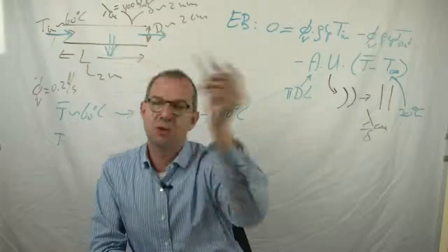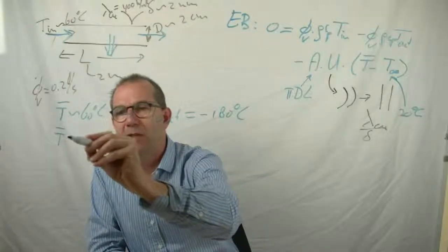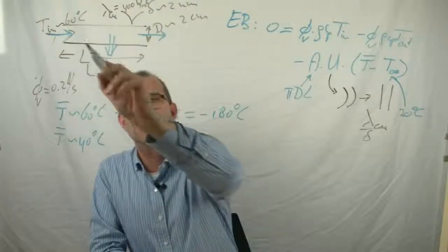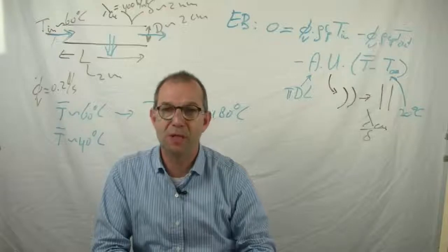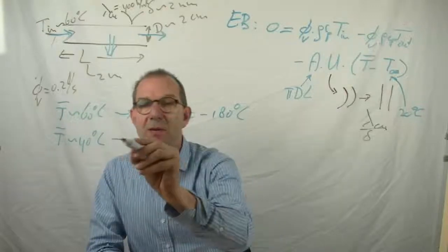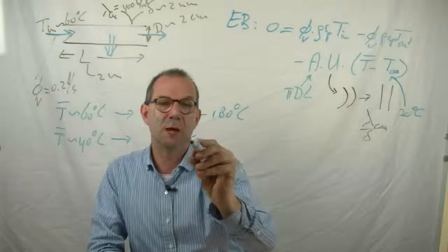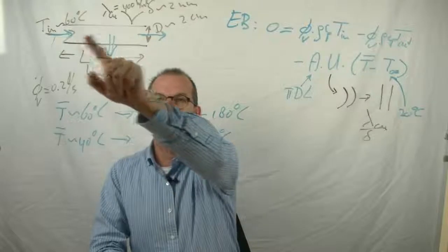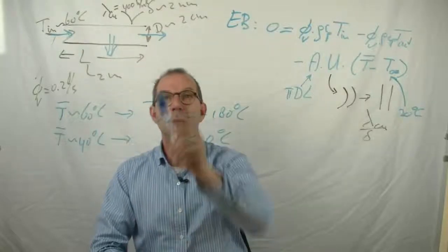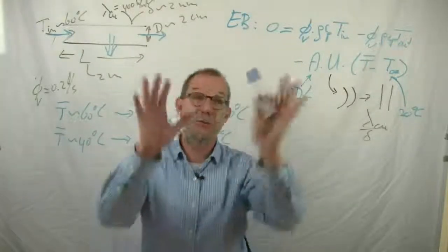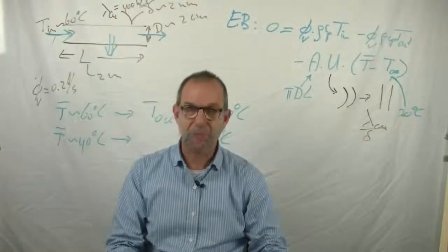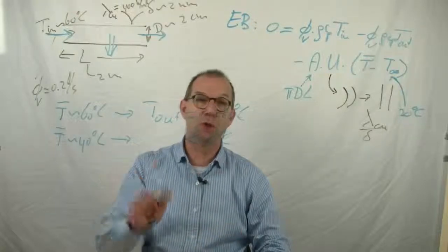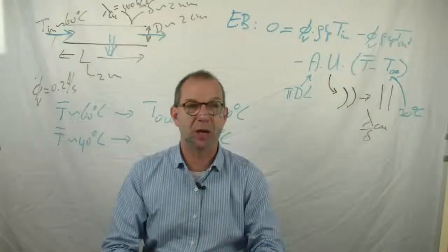I now see that this must cool down substantially. Can I get away with saying, well, it is 40 degrees at the end. It loses 20 degrees and cools down substantially. Even if I do that and fill in, I arrive at frozen water. So the conclusion is, this water will cool down really substantially, pretty close to 20 degrees, if this is the picture. And if this is the picture, you better insulate the tube, because all heat is gone in the first 2 meters. You never warm up the rest of the house.